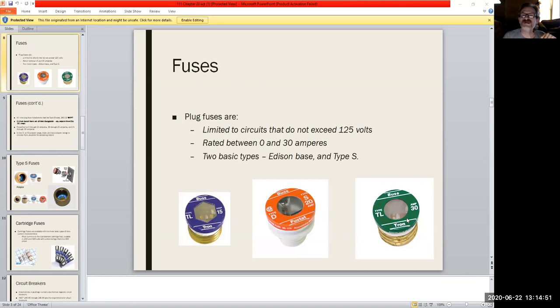Now, these are plug fuses. They were very common when I was growing up. Actually, like half the places seem to have these, and the other half were doing a new style with the circuit breakers. Now, these styles, they had pretty much from 0 up to 30 amps, and pretty much the three you see listed here are the three most popular styles they had. In fact, when I was renting apartments, you always had like a couple of boxes of each of these sitting on the service panel of your house, because if one popped in the middle of the night or something, there's no hardware store open, so you'd always have like a box of 15s and a box of 20s sitting there just in case.